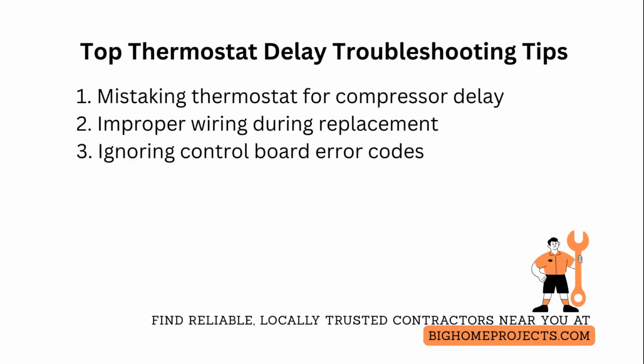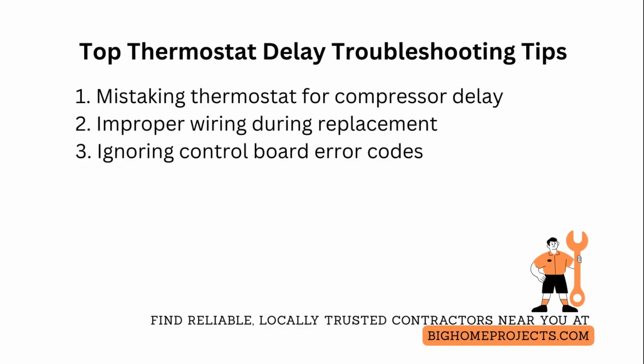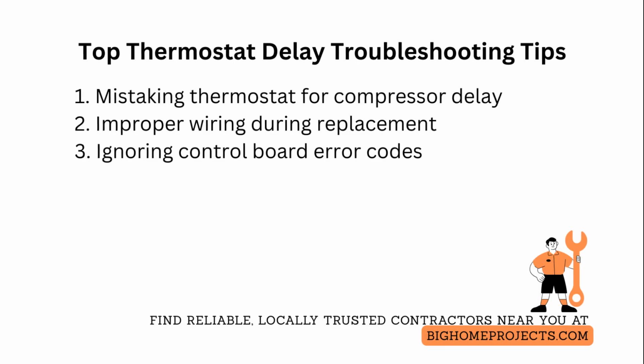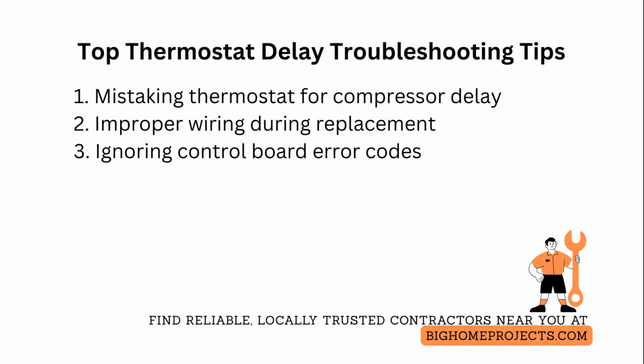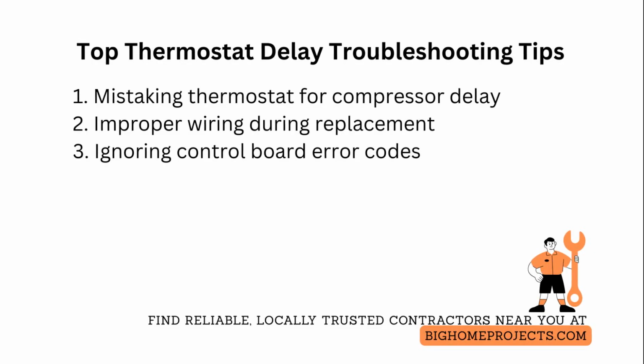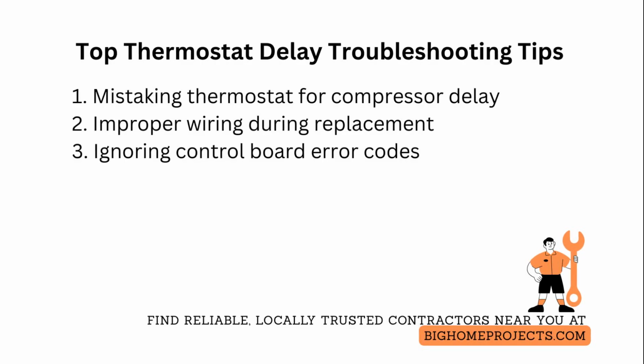One of the next common issues is improper wiring during replacement. Missing the common wire or mislabeling leads can cause long boot times or repeated restarts. Fix it by verifying the red and common connections with a multimeter, preserving the original wire colors when possible, and using a battery-backed thermostat only when common is not available.